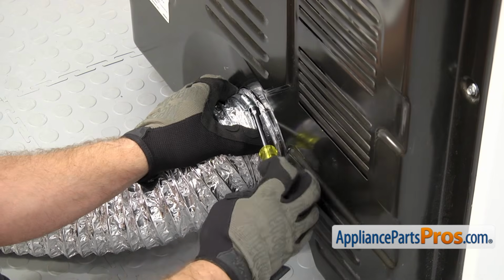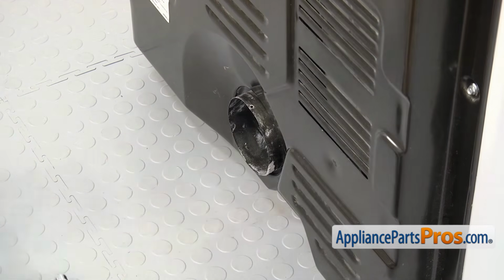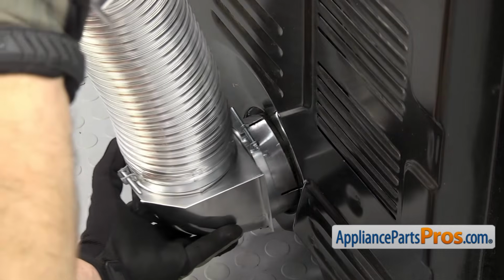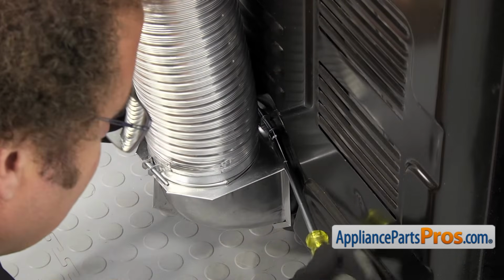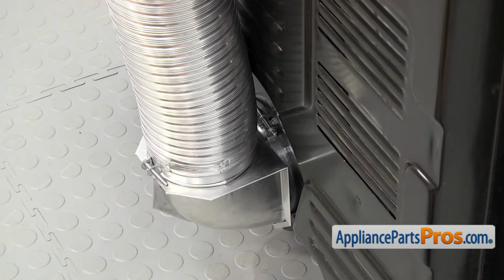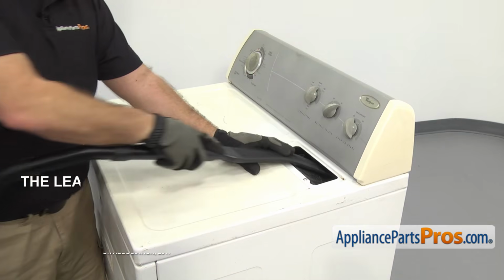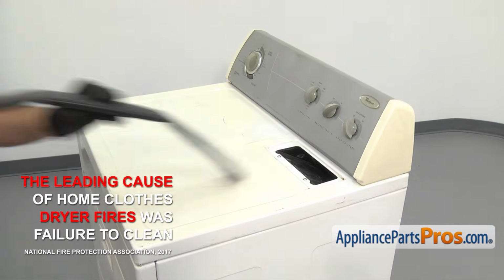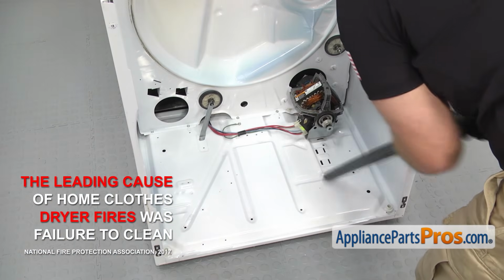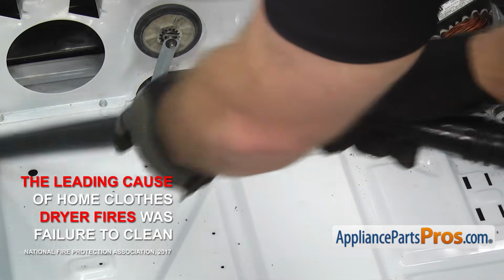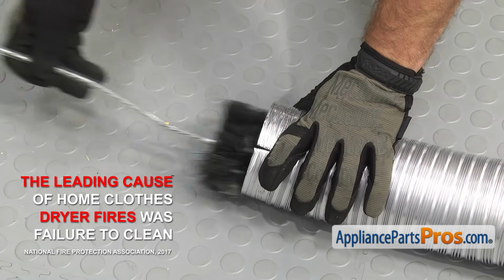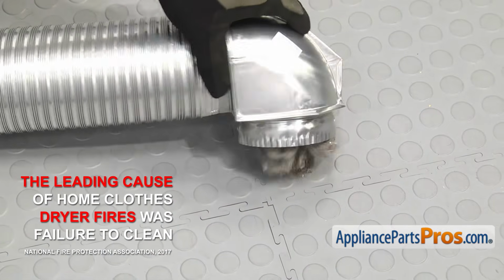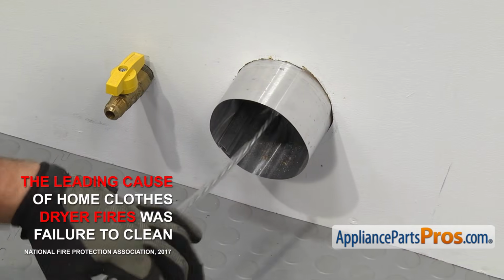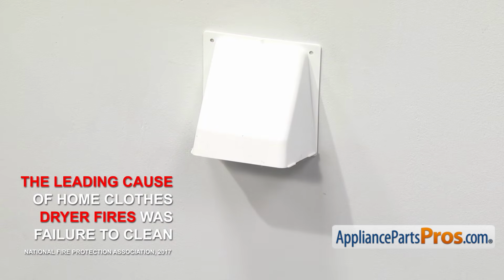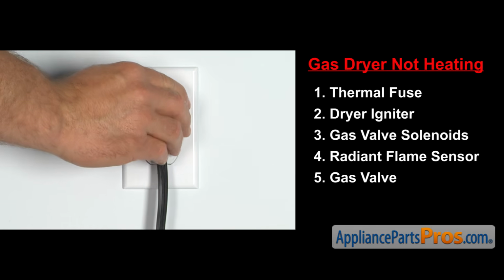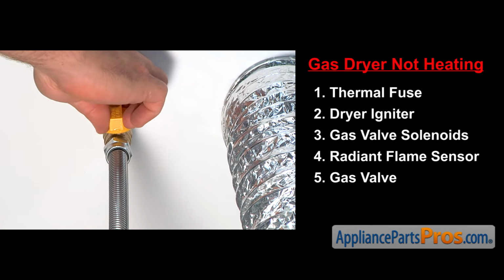If you have the flexible style ducting, it's recommended that you upgrade to the rigid metal kind to prevent lint buildup and the duct from accidentally being crushed. Make sure you follow the manufacturer's instructions when installing new venting. Failing to clean the dryer is the #1 cause of these fires, so make sure to clean the inside of the dryer, including the lint screen and blower housings, the ducting from the back of the dryer to the wall, and from the wall all the way to the outside of the house at least once a year. Once you take care of the problem, you can plug the appliance in and turn the gas back on.